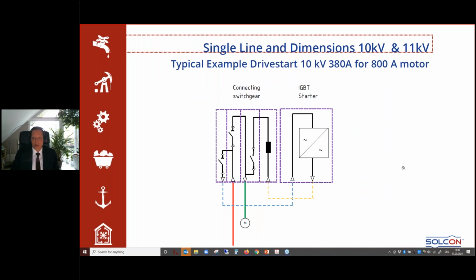Okay, just to give you a practical example, something that we have quoted recently. Here you see in principle the topology of the switchgear portion and the IGBT starter. You come in from the line from the customer. You have here a vacuum circuit breaker. This is the bypass. You have here a vacuum circuit breaker protecting and connecting to the IGBT starter. Output of the starter going into an output reactor with 3% impedance. You have here a vacuum contactor, then feeding to the motor. The motor is starting. Then you close the bypass and open this as the motor is at the network. All the switching elements here are withdrawable with earthing switch possibilities in order to have LSC2B rating here for the inverter, so that when the motor is running, you can do some maintenance work here.